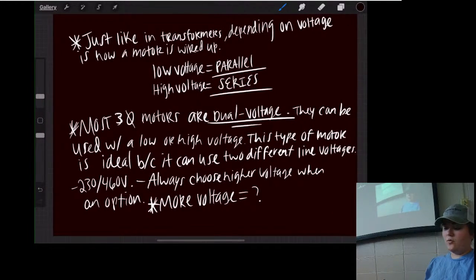Just like in transformers, depending on voltage is how a motor is wired up. If it's low voltage, what do you need? Parallel. If it's high voltage, what do you need? Series, right? Just like the transformers, remember how if we wanted to step down from 480 to 120, what do we wire it up in? High voltage, remember - 480 is your high. So if we wanted to step down that transformer from 480 to 120, we wired it up in series. But if we wanted to step it down from 240 to 120, what did we wire it up in? Always remember: low voltage equals parallel, high voltage equals series.